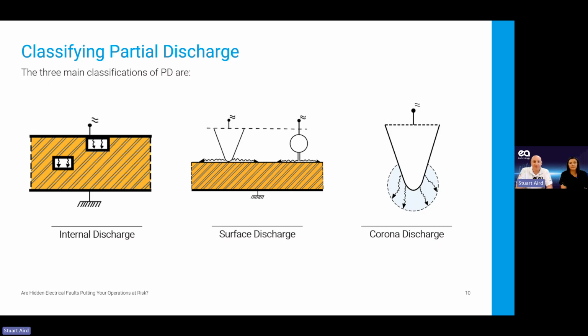Then the final one is corona partial discharge. That's something that's just too sharp. It's got too pointy at the end, and basically it will not be able to control its electrical stress in that area. You hear it a lot on overhead lines on a rainy day. It's been a couple of weeks since we've had a rainy day in the UK now. But if you hear overhead lines cracking, that's probably not too much of a problem. But if you've got something that's been cut too sharp within a switchgear panel, it will create ozone and acids within that panel, which will lead to surface-related partial discharge as well. So again, the best sensor type for that is going to be ultrasonic, because that's going to be the most sound. Again, corona can create quite strong electromagnetic waves as well.